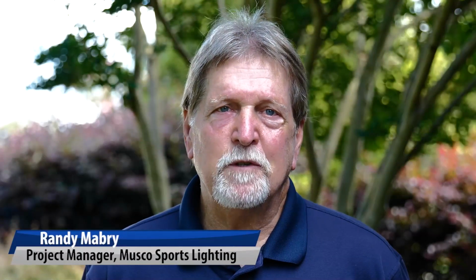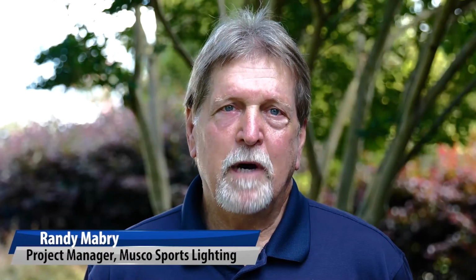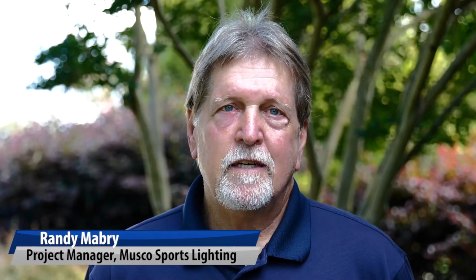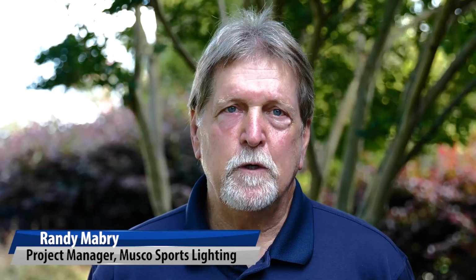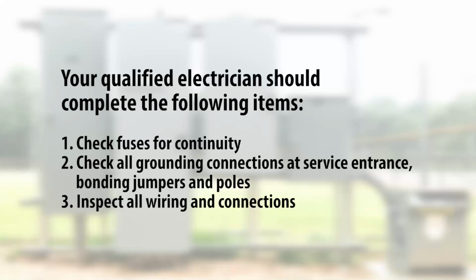Many of these items on the checklist should be performed by a qualified electrician. Greg Newell will take us through testing many items on that checklist. Stray voltage can occur on any conductive material. For example, fences, metal poles, aluminum bleachers. This can be found and isolated through a process that needs to be performed by qualified electrical personnel.